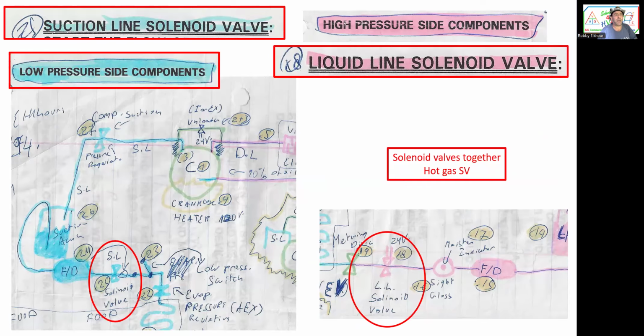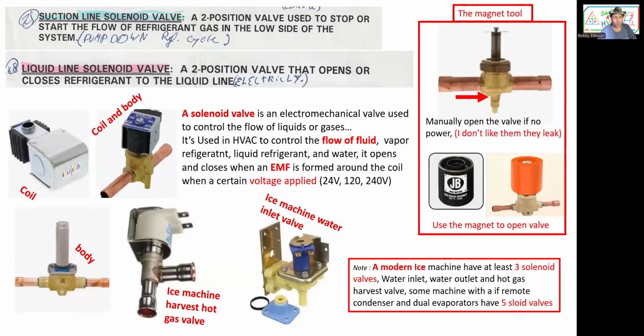Next, we have the suction line solenoid and liquid line solenoid. We put them together because solenoid valves go together. Solenoid valves are a very big part of refrigeration. In air conditioning, not as much, but in modern air conditioners, yes. Because with Freon 410, the pressure on the high side is so high that the liquid receiver can't hold it on shut off. So they need a solenoid valve to shut off the liquid line.